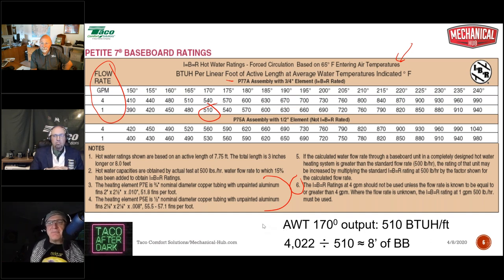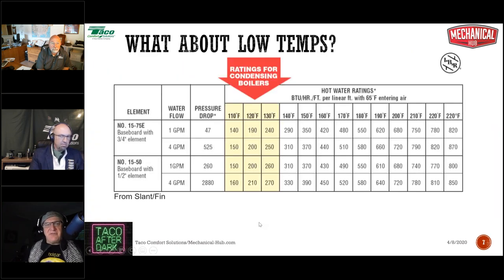Well, let's take a look at lower and lower water temperatures. You see the Petite 7, Sterling rates the Petite 7 down only as low as 150 degrees. But if we were to look at a different brand, Slant/Fin actually rates their baseboard down to about 110 degree average water temperature, where you're going to get a heck of a lot fewer BTUs per foot. If you make baseboard, what a great idea, right? But you can see it's rated to much, much lower temperature.